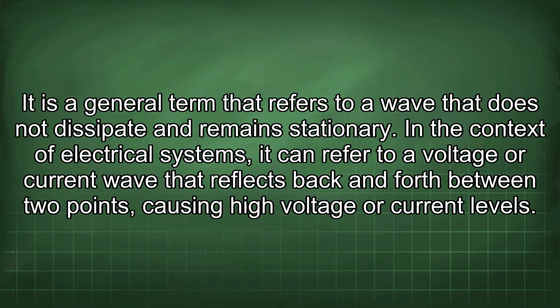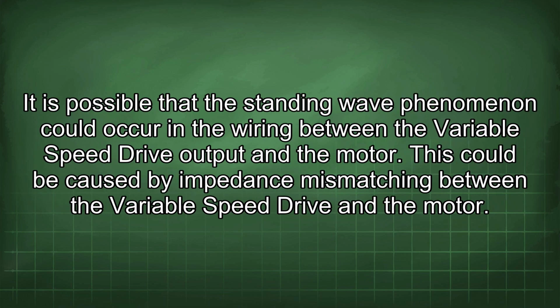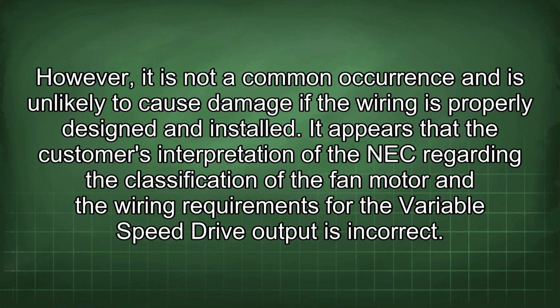It is a general term that refers to a wave that does not dissipate and remains stationary. In the context of electrical systems, it can refer to a voltage or current wave that reflects back and forth between 2 points, causing high voltage or current levels. It is possible that the standing wave phenomenon could occur in the wiring between the variable speed drive output and the motor. This could be caused by impedance mismatching between the variable speed drive and the motor.